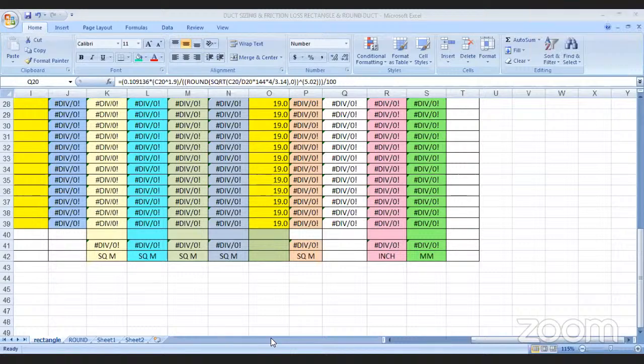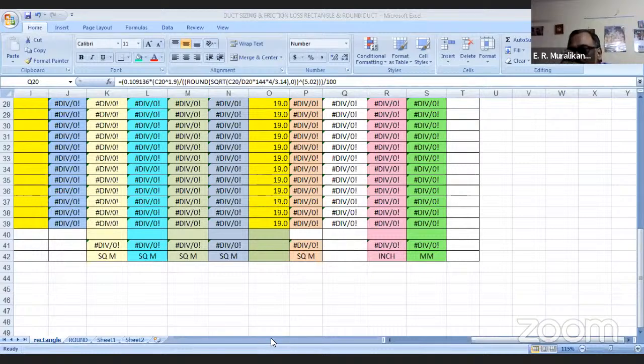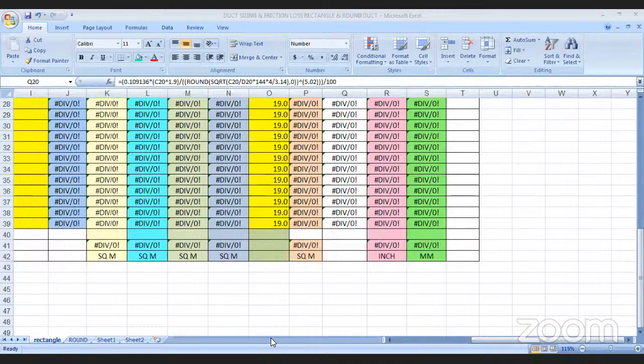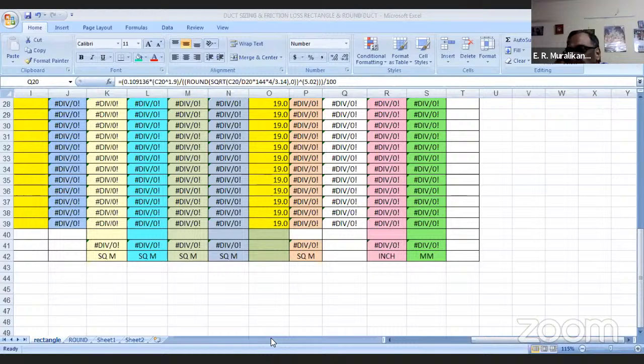Please specify what is the ratio for supply air duct and return air duct sizing. See, either way, this is geometry, which means this much square feet of air should come, this much velocity you should have. You can go for rectangle or round or square or elliptical. It's up to your choice. That again, I'm telling you, aspect ratio. If you have a very good aspect ratio, there will be material cost saving. If your aspect ratio is not good, then your material cost will be high because the gauge changes. And CFM, you already work out how much should come. Please maintain a low velocity, 1200 fpm, and do not go beyond that. Otherwise your friction loss will go very high. You may save on duct height and width, but your friction loss will go high.